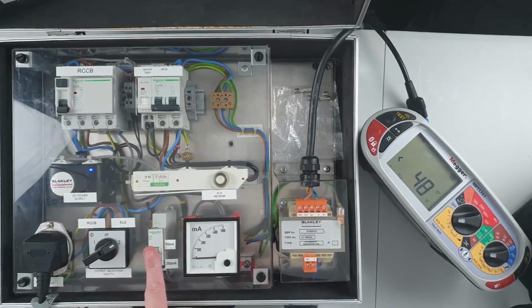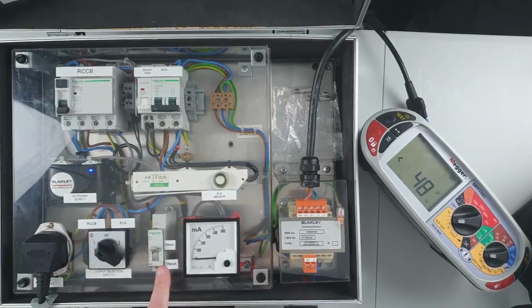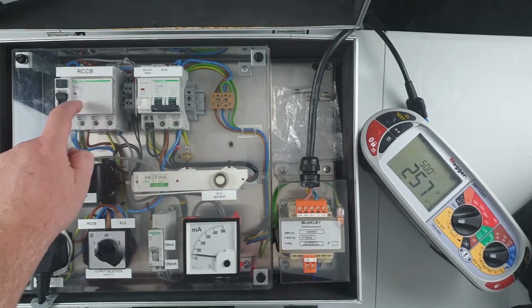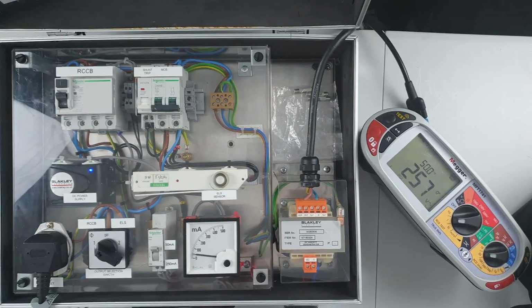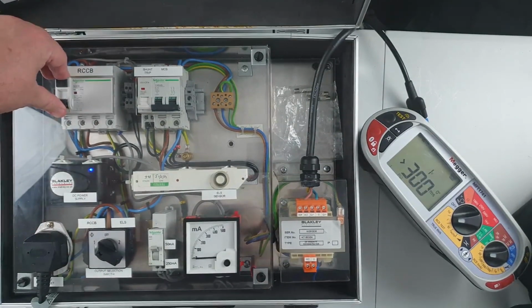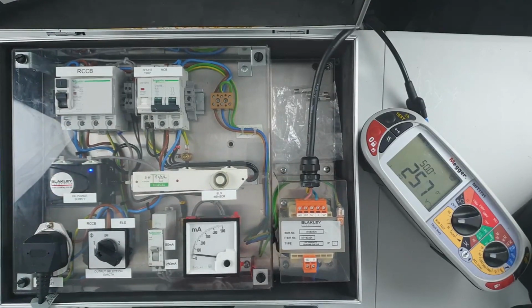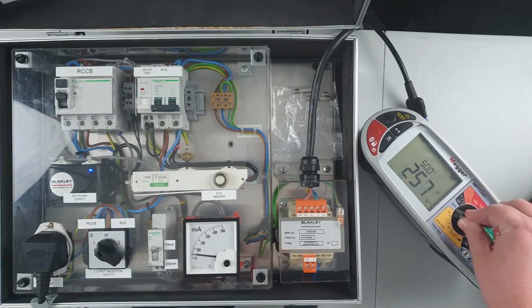So let's introduce 50 milliamp of DC leakage into the system. And we'll just play with this RCCB here for now. So having introduced 50 milliamp, we now have a no trip scenario. So this is sufficient leakage of DC nature to put this RCCB off. It still works functionally, but it's not tripping. We could chase this down to actually discover how much milliamp will be required to disconnect this by upping the test here. So if I go to times half at 100, that's a 50 milliamp test.